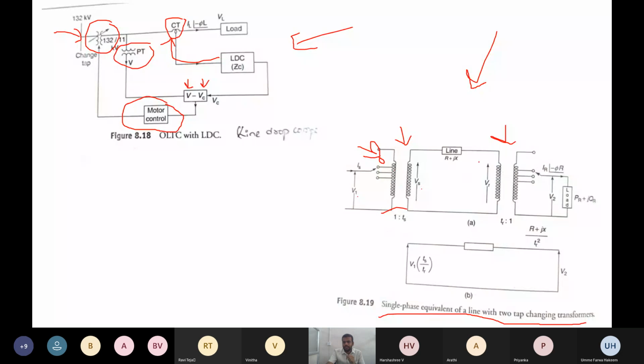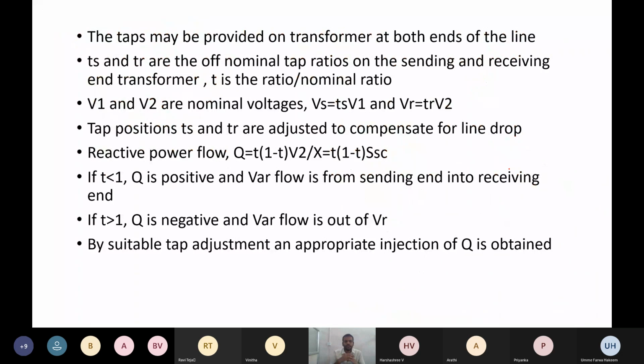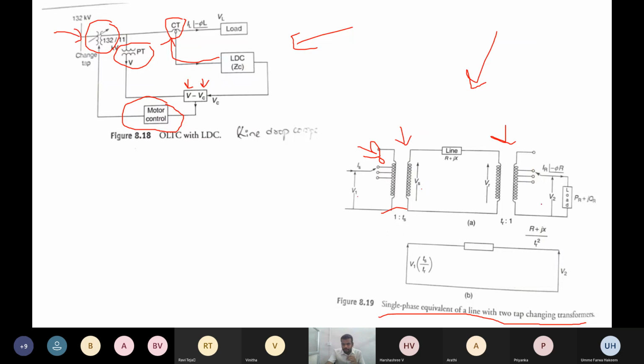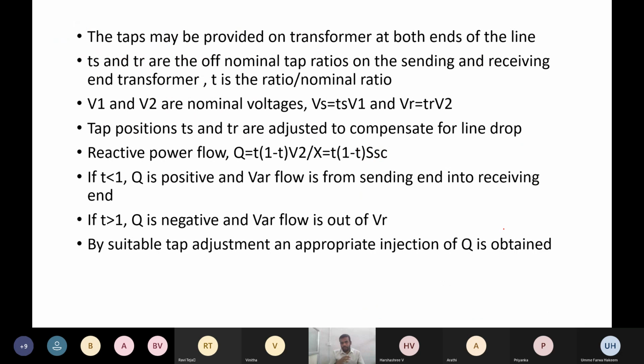So this is one kind of tap changer, and this is another kind of tap changer. And Ts and Tr are the off nominal tap ratios of the sending end and receiving end transformers. So T is the ratio of the nominal. V1 and V2 are the nominal voltages. So Vs will be given by Ts into V1, and Vr will be given by Tr into V2.